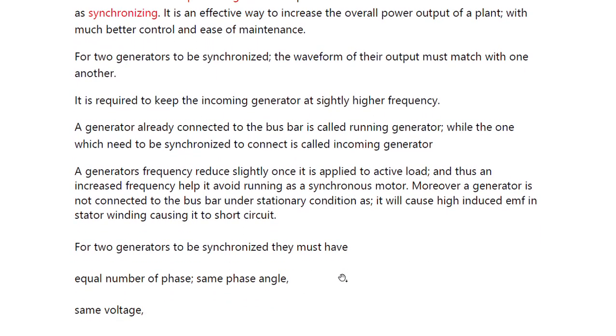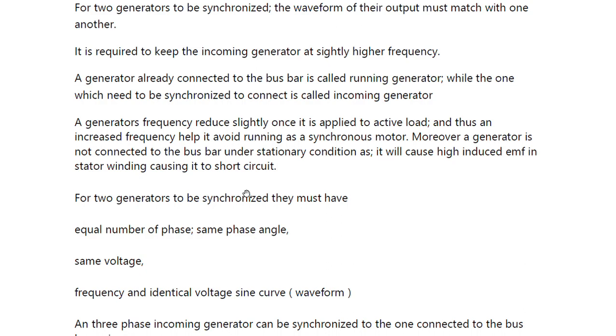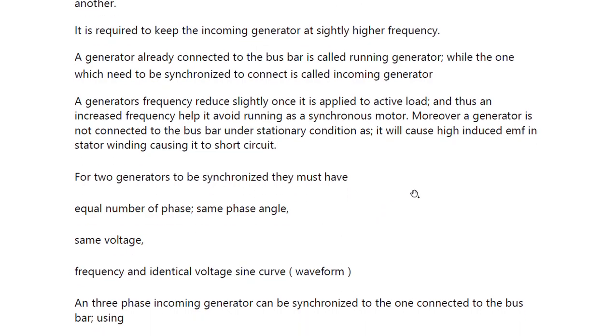For two generators to be synchronized, three conditions must be met: equal number of phases, same phase angle, and identical voltage — meaning the sine curve or waveform has to be the same. Additionally, if the running generator is connected with RYB phase sequence, then the incoming generator must also be connected in the same fashion — R to R, Y to Y, B to B. It cannot be R to Y.